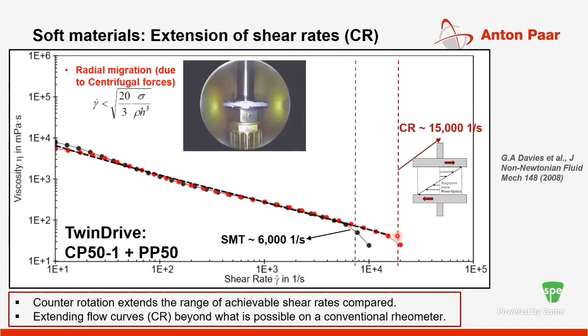This is unique because of the stagnation plane which is created when you move the two motors. If you divide the deflection equally, 50% each, with equal speeds, you can create a stagnation plane, and that reduces the gap to h/2, and then you can extend the characterization range. This is relevant because many flows in nature, like microfluidic flows, lubrication flows, coating flows, or flow through nozzles, need high shear rate characterization. And typically it's very difficult to measure on standard rheometric configurations. Hopefully I'll show you some data in the next slide where this becomes more clear.